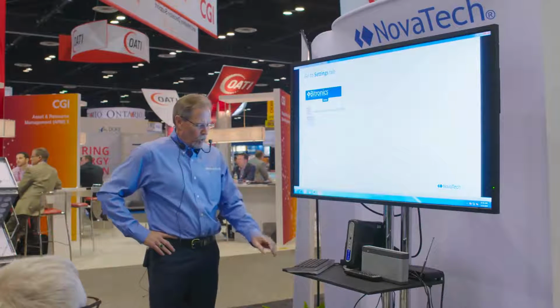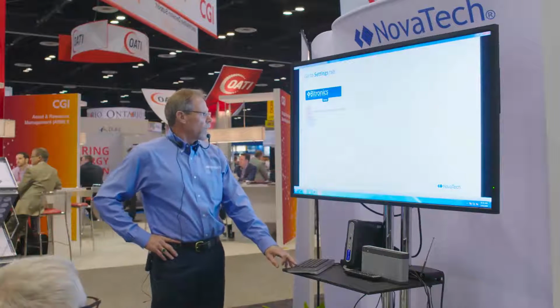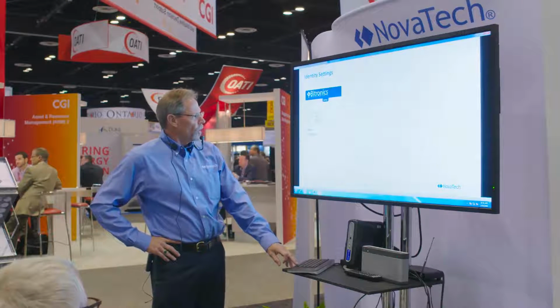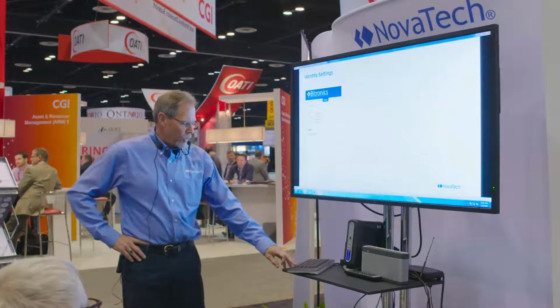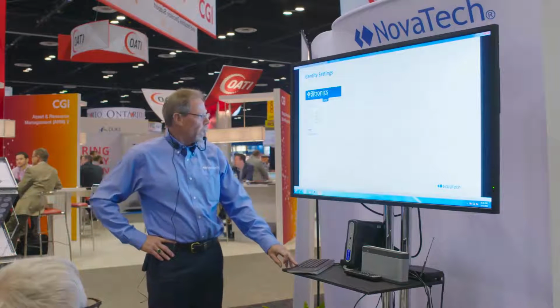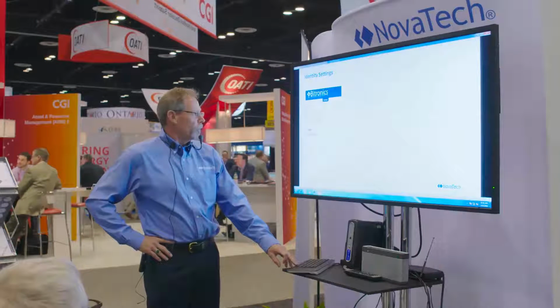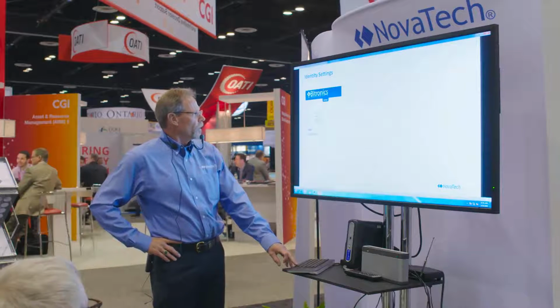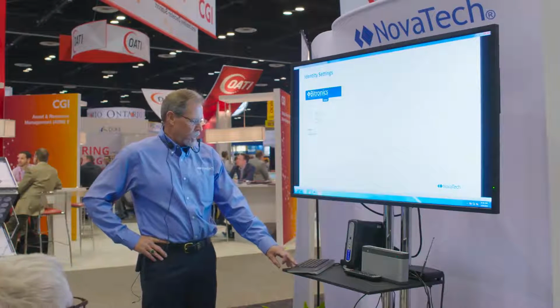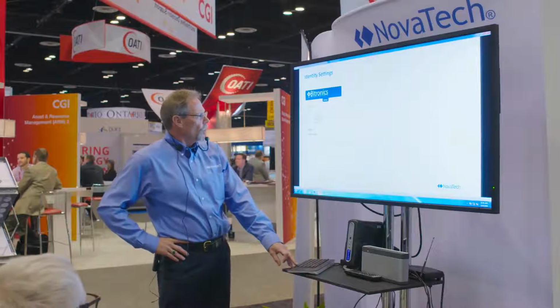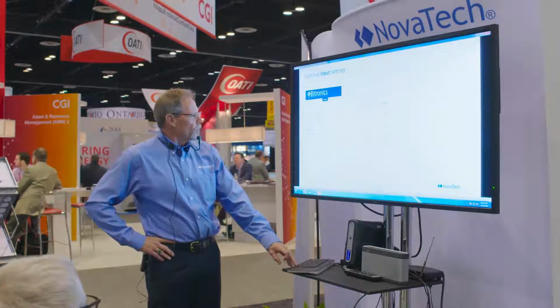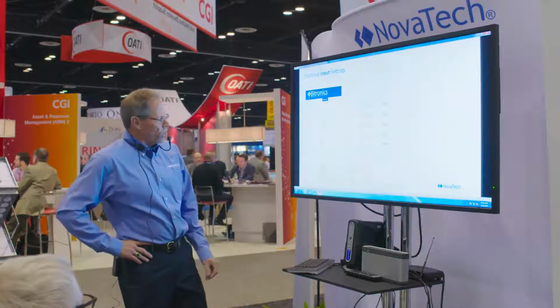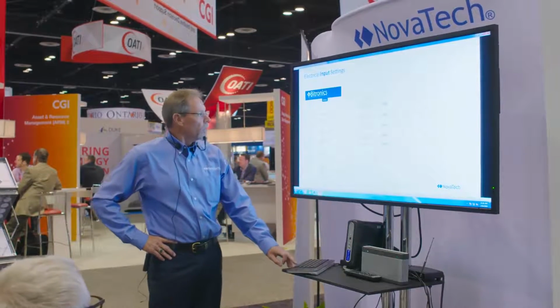The first thing we're going to do is we're going to go in, set up some unique settings for the device. We've got some options like feeder names if you want to, or a substation name. Not necessary to make the meter work, but comes in handy if you're doing configuration files, maintenance, etc. This is the setting screen that you pull up.